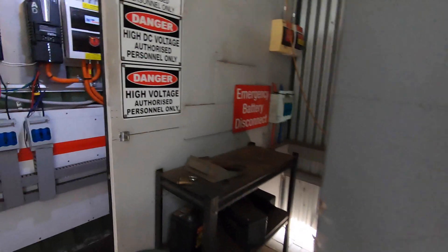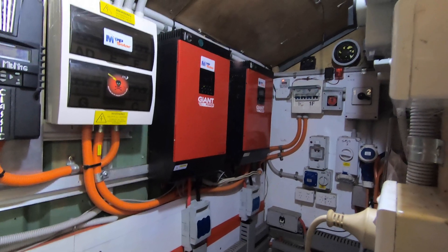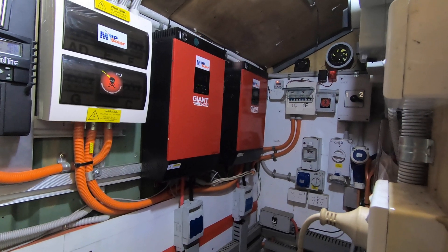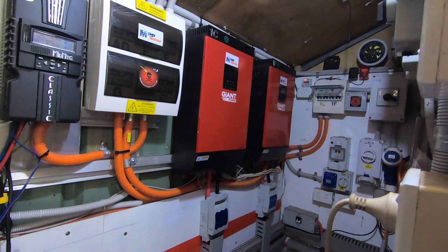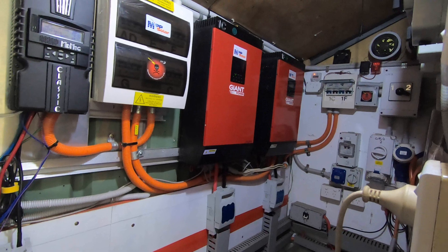The inverters went to shutdown voltage. I've got them set to shut down at around 80%, which they did — the voltage dropped down to the shutdown voltage at about 82% and the inverters turned off. We were scratching our heads because we didn't realise what was going on. We checked all the isolators — everything was fine. Then I looked at the voltages, which by then had climbed back up, everything turned back on again, and I thought: okay, that's the problem.